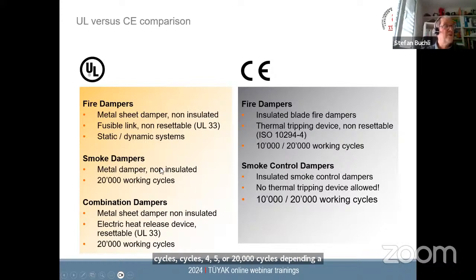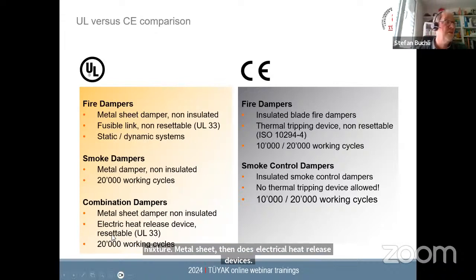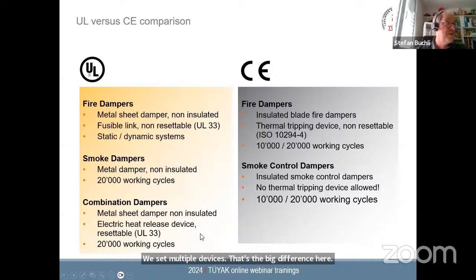Then on the smoke dampers, you have also here on the UL side, non-insulated metal sheet dampers, 20,000 working cycles. Smoke control in Europe: you have insulated dampers, no thermal tripping device allowed. And here you usually have 10,000, 20,000 cycles. And then the combination dampers, it's a little bit a mixture. Metal sheet dampers, electrical heat release devices, resettable devices. That's the big difference here. You can reset one device at least, and 20,000 working cycles.